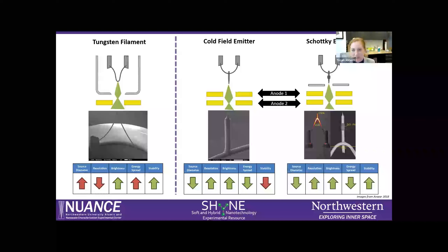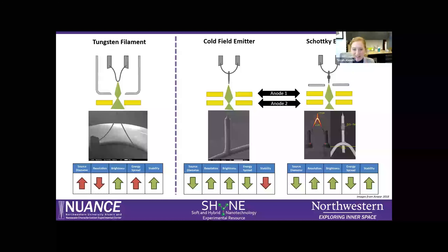One of the most popular sources today is the Schottky field emitter, sometimes called the heat-assisted field emission gun, because they are heated to about 1800 Kelvin. They're coated with a zirconium oxide tip, which further reduces the work function, and there's a zirconium oxide reservoir so the coating can replenish itself over time. They do only last about two to three years. These sources have the best of everything: a really small tip for high-resolution imaging, lots of current for microanalysis, very stable beam current because it's heated at a consistent temperature, and a small energy spread.